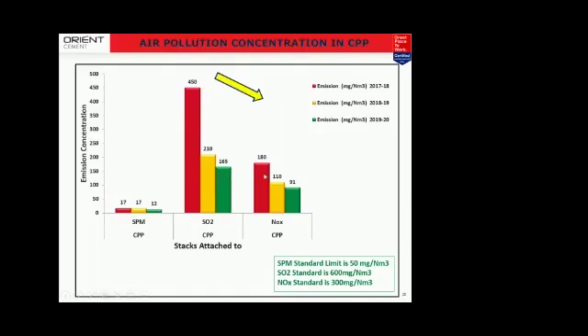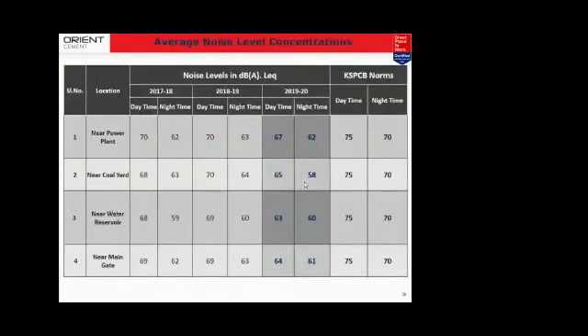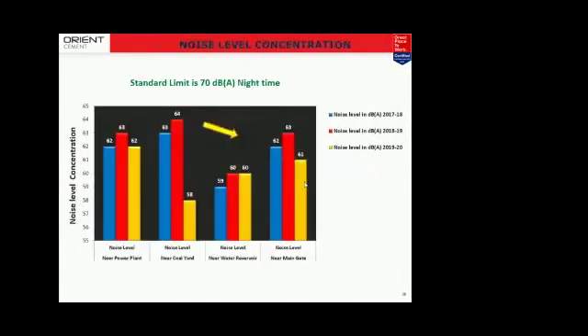And also NOx, since we have increased the load and we have also fine tuned the boilers with the 3 T's, that is temperature, turbulence and time, with that also we were able to achieve low NOx. Since we are using G13 coal, it has a high ash content and low sulfur content. Also our boilers are designed for 70% ash content, so it is a very good boiler design provided by ThyssenKrupp. These are just the noise levels which we had.